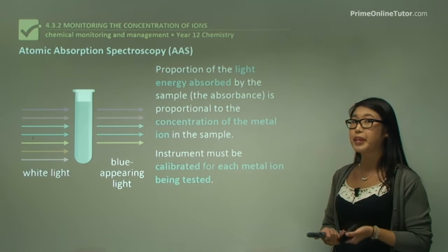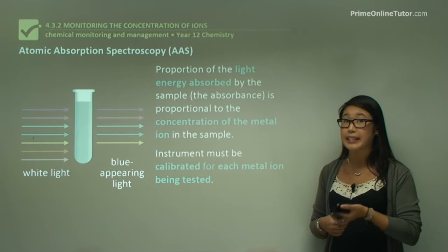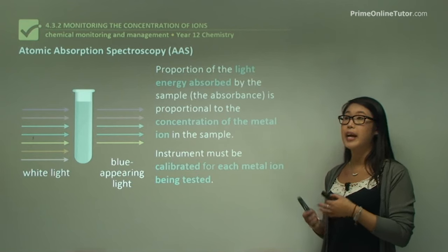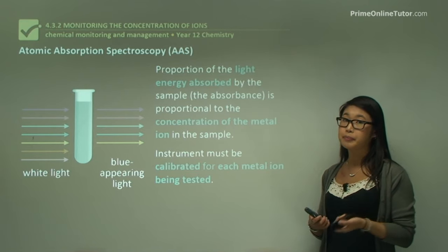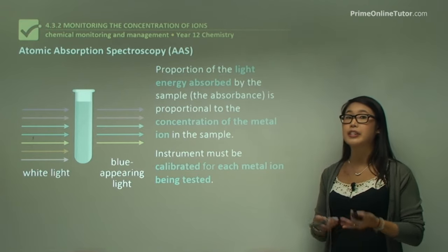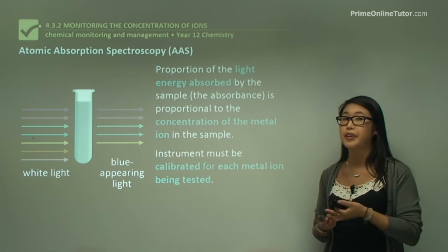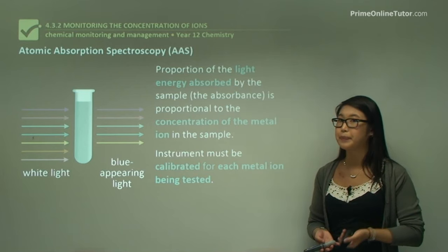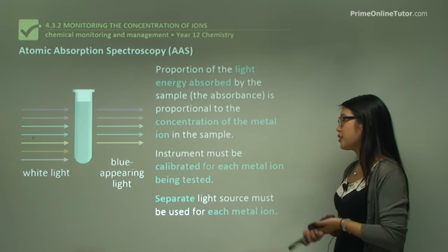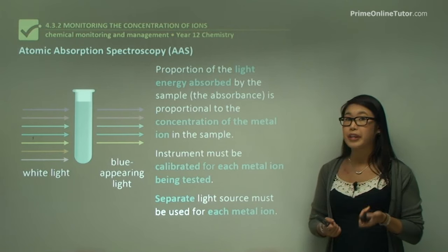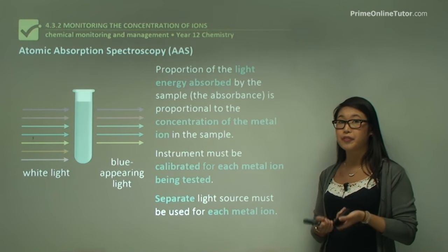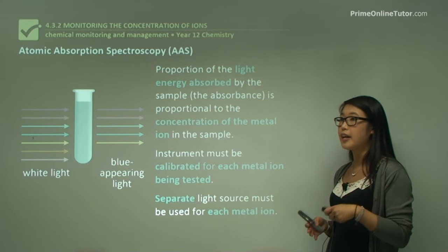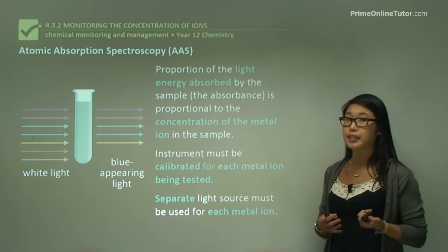The instrument must be calibrated for each metal ion being tested. If we're looking for copper, we calibrate for copper; if we change to zinc, we calibrate for zinc before analyzing the sample, otherwise it won't work. Separate light sources must be used for each metal ion because each is specific for that ion.